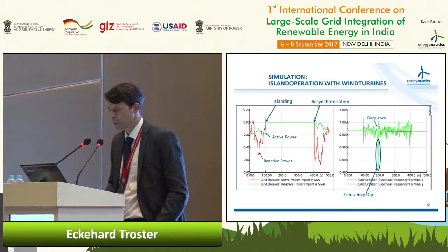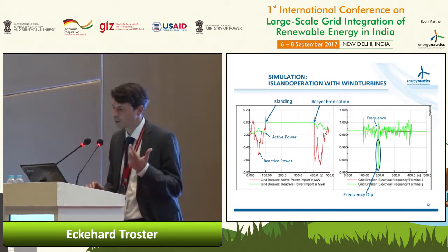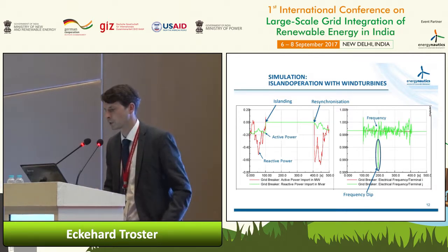And then we went into island mode. So there's no exchange during this period of 400 seconds or 300 seconds to the overlying grid. And then we came back. So resynchronization. And you can see this here, where you have a very stable frequency during grid connection. You can hardly see anything.